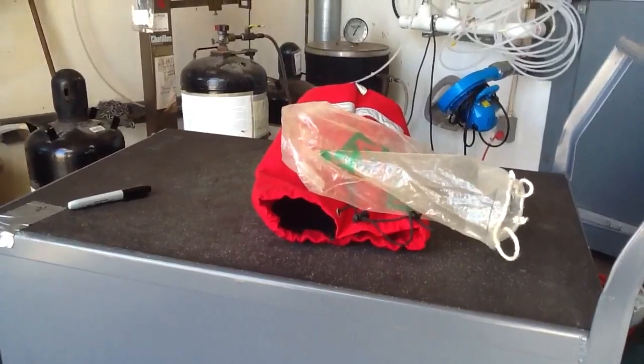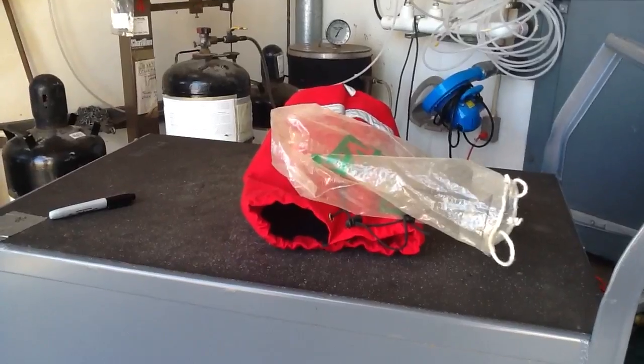And also, to check for leaks — now at Port Everglades we do a lot of container inspection, so you want to check for leakage. You've got a halide detector; it's almost like a bunch of burners, and you just go around the door to check.